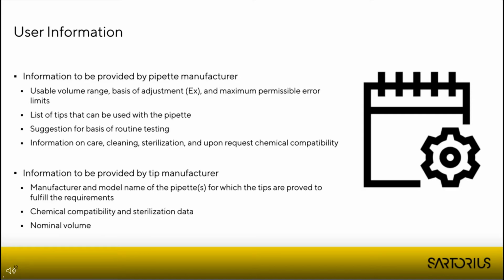There is no established way in the market to do this as of yet, but I would assume there is going to be a list of the same manufacturer's tips. And then a suggestion for the basis of routine testing. Again, I want to highlight this is just a manufacturer's recommendation. It does not bind the user. So the user in the end is still responsible for creating the testing procedure, how often to test, how to test, etc. Then information on care, cleaning, sterilization, and upon request, chemical compatibility.